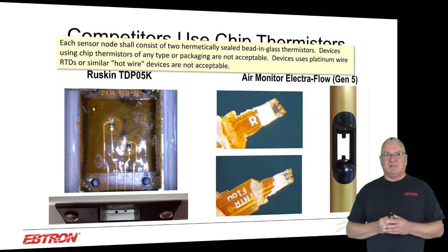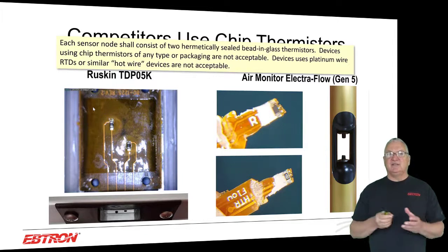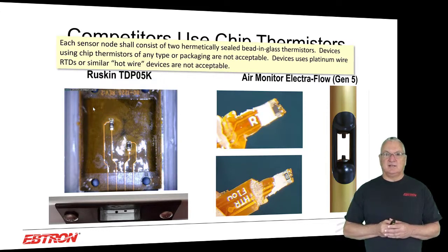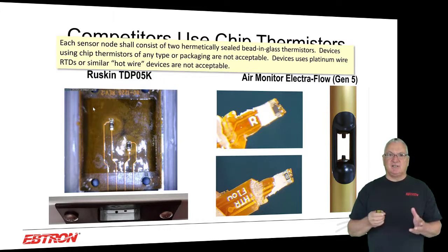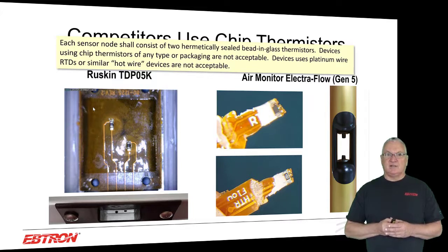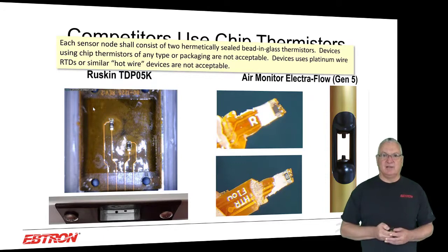Devices using chip thermistors of any type or packaging are not acceptable. I mean, that basically eliminates the Ruskin and the air monitor product. And devices using platinum wire RTDs or similar hot wire devices are not acceptable. You may run into some thermal hot wire devices that are trying to get some of your jobs. Typically speaking, hot wire is good for industrial applications because of the way it's manufactured, but honestly, I don't think it's as good of an airflow meter.